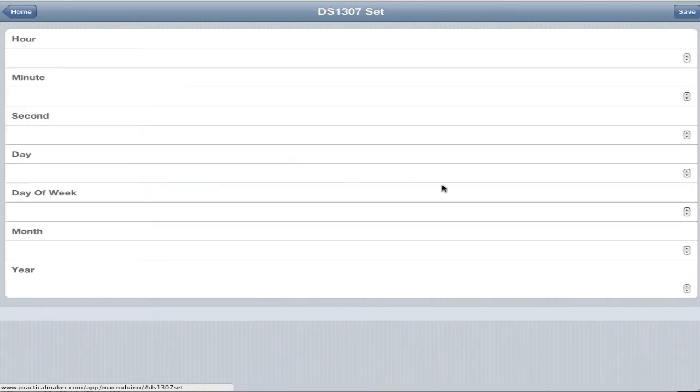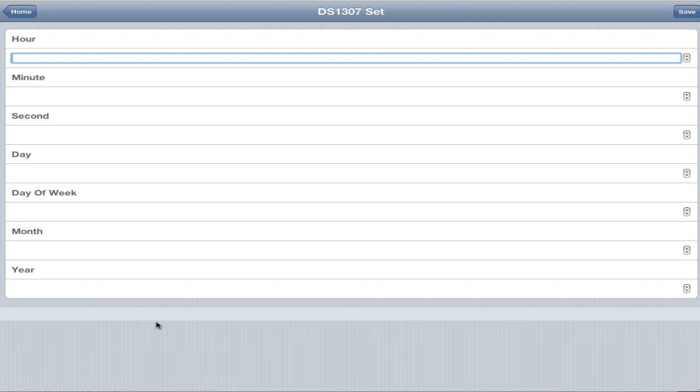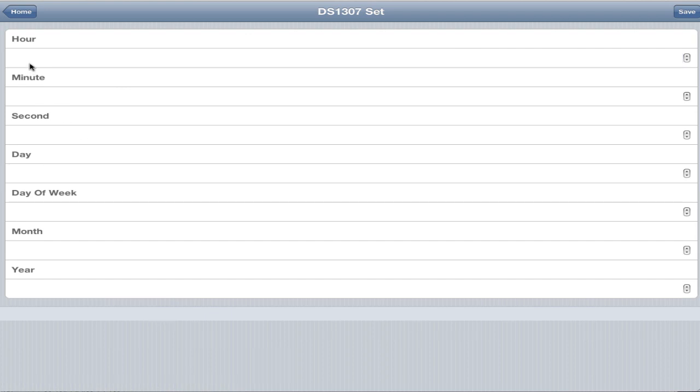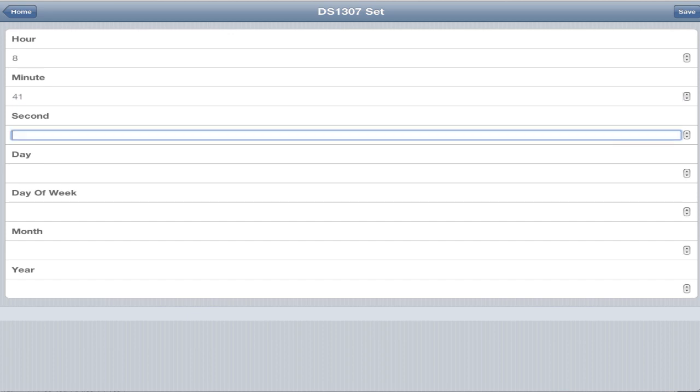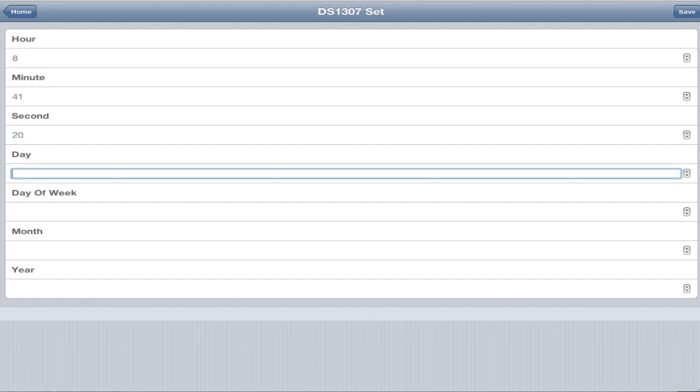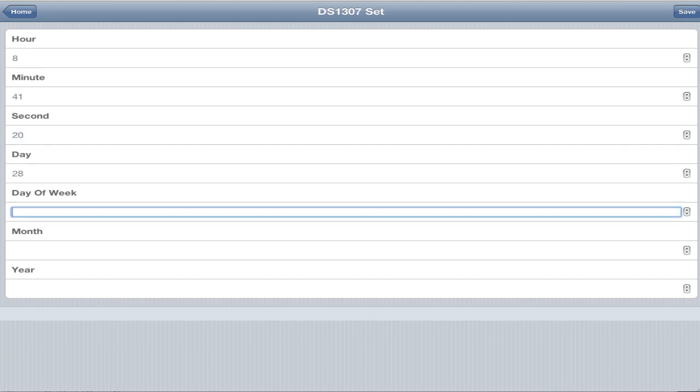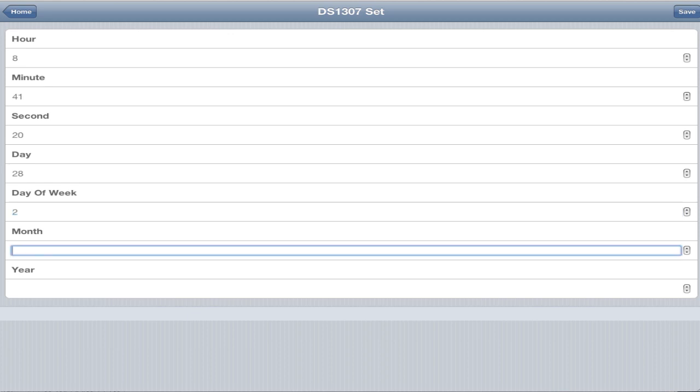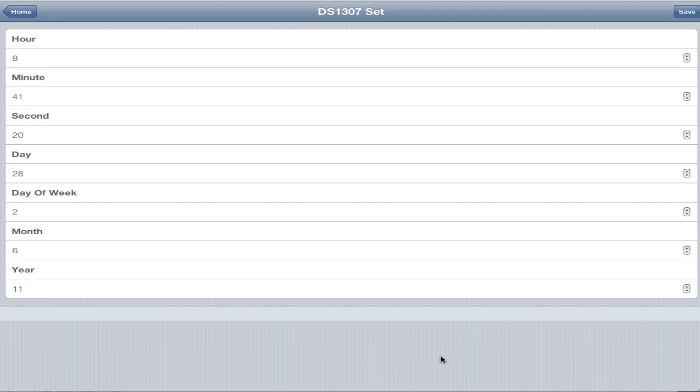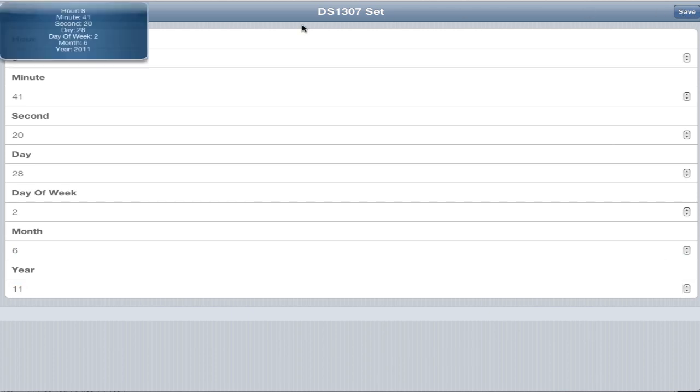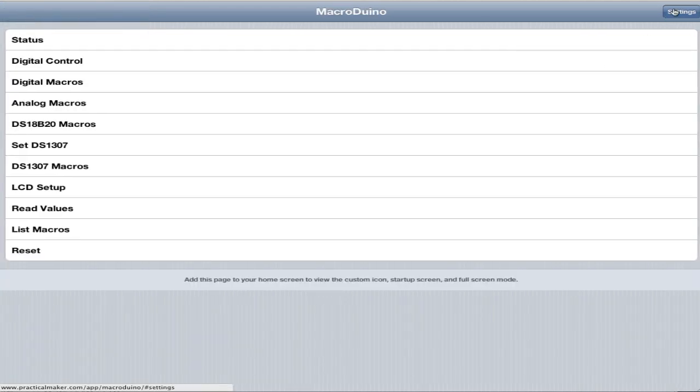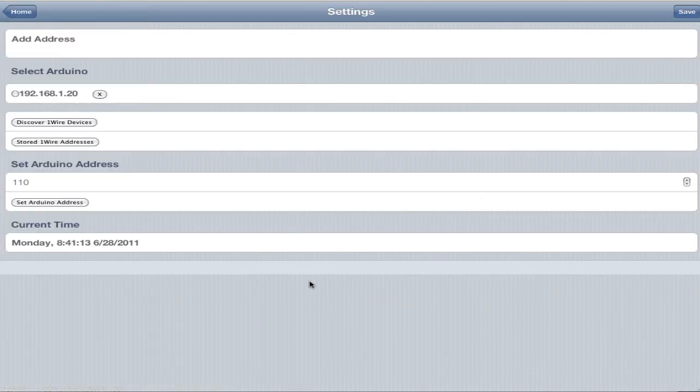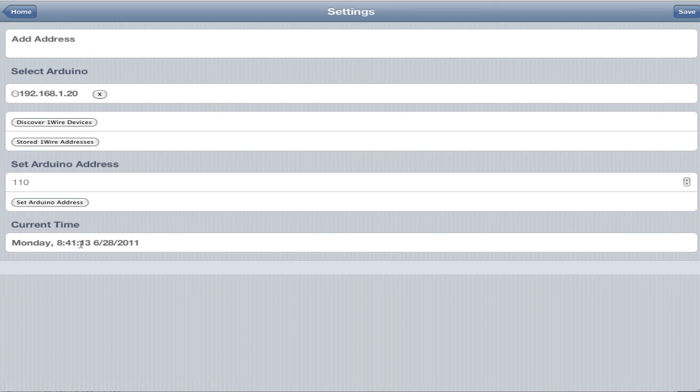Setting the time on the real-time clock is extremely simple. It's in 24-hour time. We were a couple minutes off when we checked, so we're going to set it correctly now. 8:41, second 20, day 28. Day of week, it was Tuesday. I don't know what the day of week is, just play around with it. Month six, year last two digits, so it's 11. It pops up with what you sent to it so you can verify that it went through correctly. We'll go to settings and check that this is set. Tuesday is day two. We set it to 8:41, which seems like everything worked.